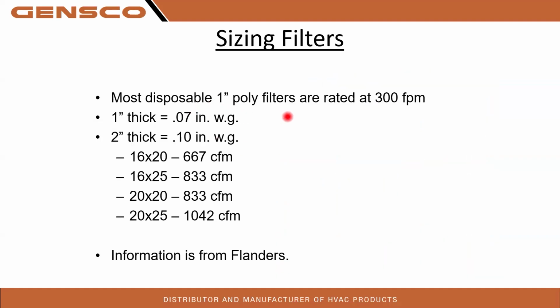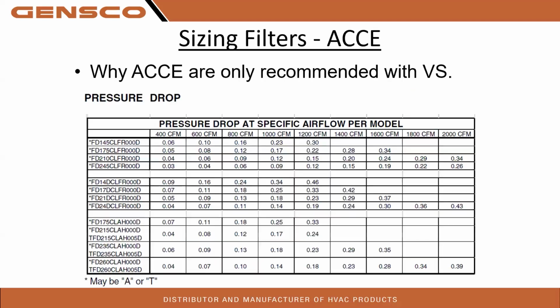Most disposable 1-inch poly filters are rated at 300. So the 1-inch filters are rated at 300, and it's rated at 0.07 pressure drop. The 2 inches are at 0.1. Okay, so this is from Flanders. These are AccuCleans and Clean Effects.